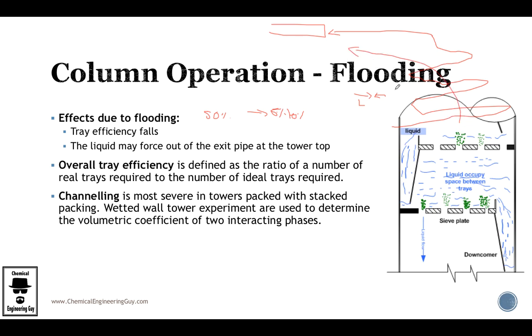Now, there is also a certain point in which maybe you are in steady state. So all the column is flooded and it's kind of hard to see that you are actually flooding the columns. So you can be operating this right here at flooding conditions. And because there is not excess going back or going through here, you will not see this flooding because of course this is covered in steel.